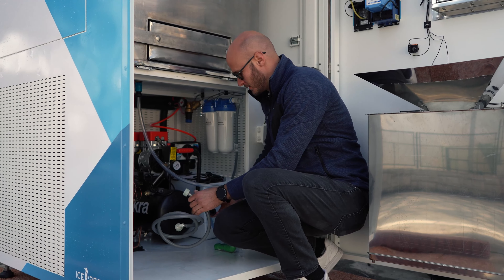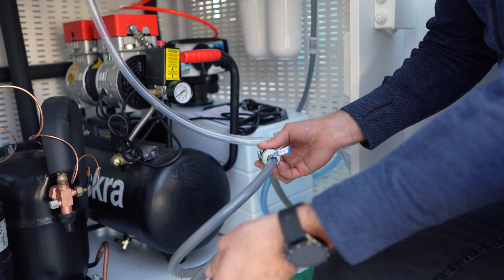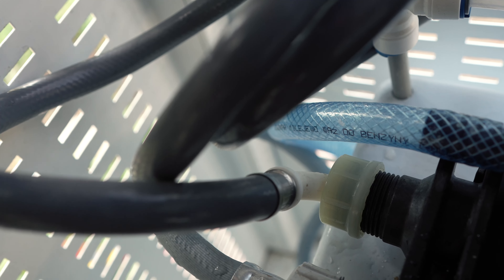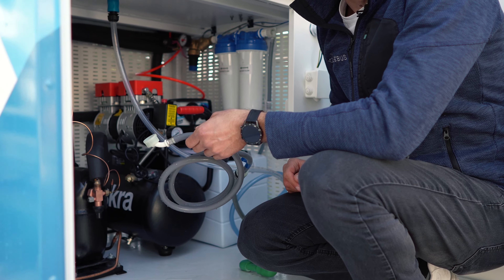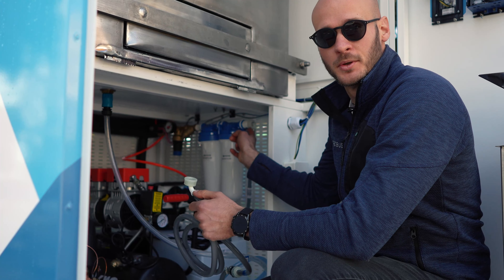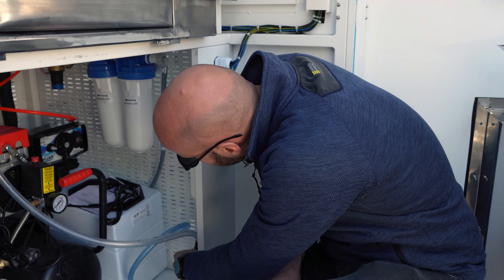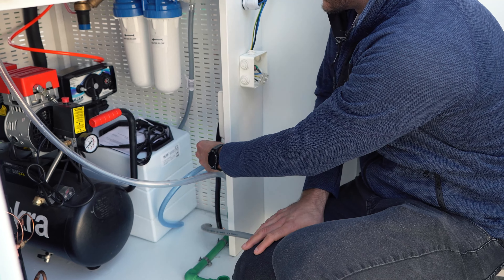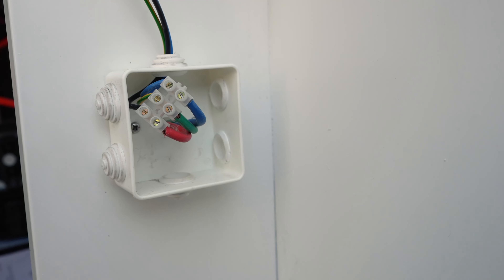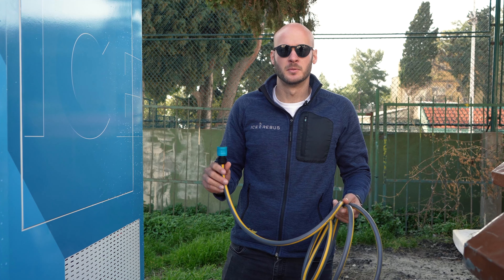We will connect the water hose like this, then connect the other side to the depurator. If your machine comes without a depurator, then you connect this part straight to the water filter. Now we will connect the electricity — the connection cable goes through this hole, and through here we will connect it to these cables. The last part of the connecting: we will connect the water drainage.